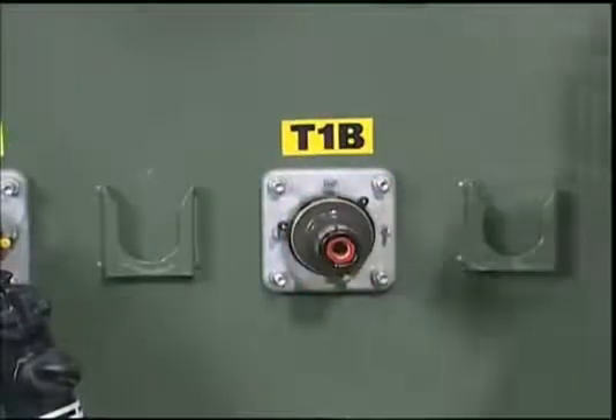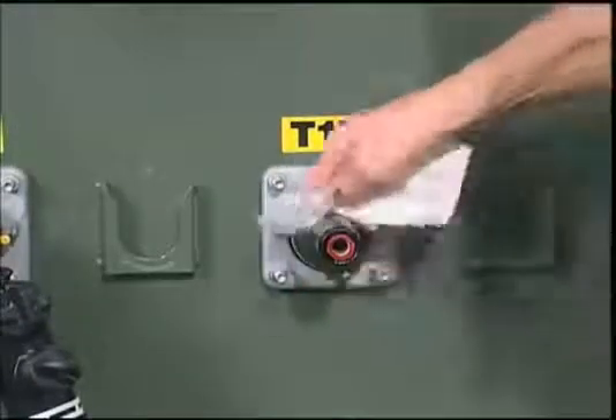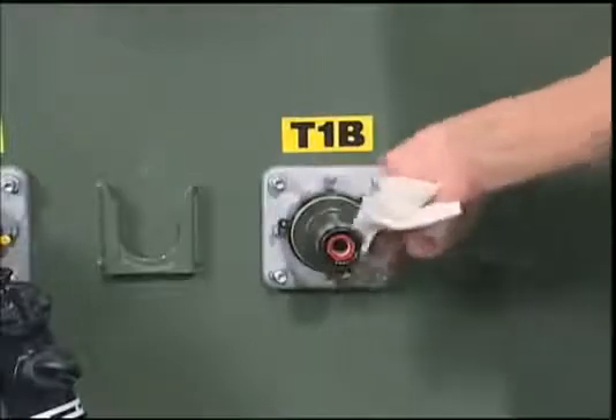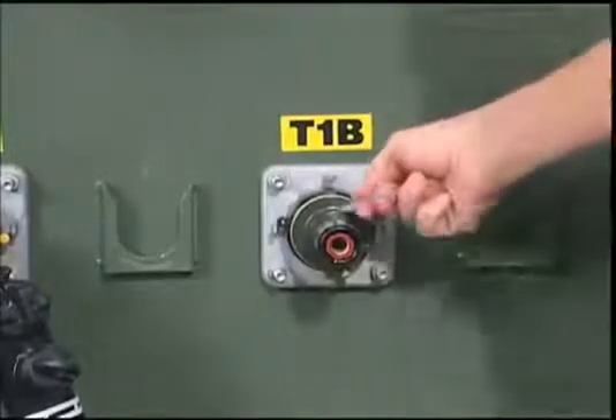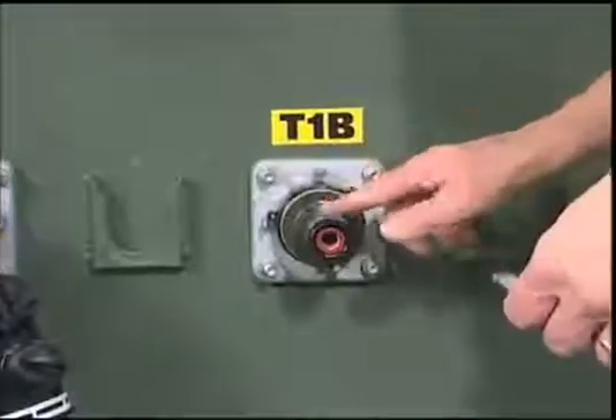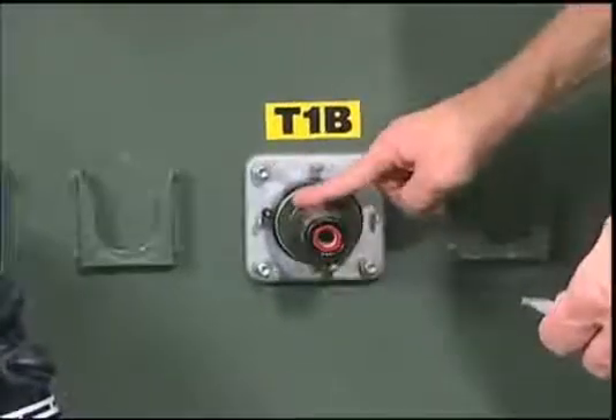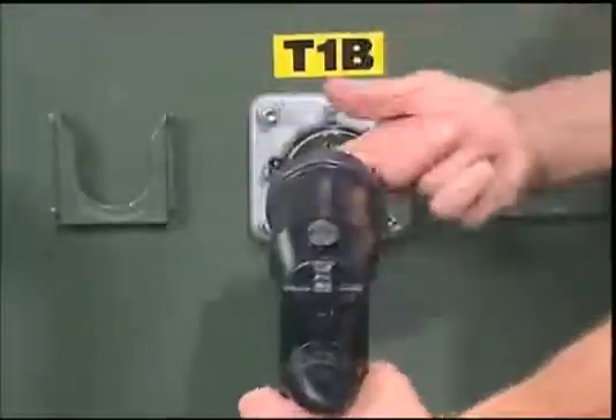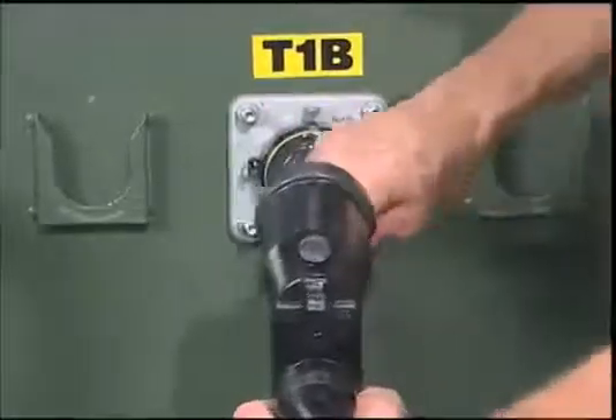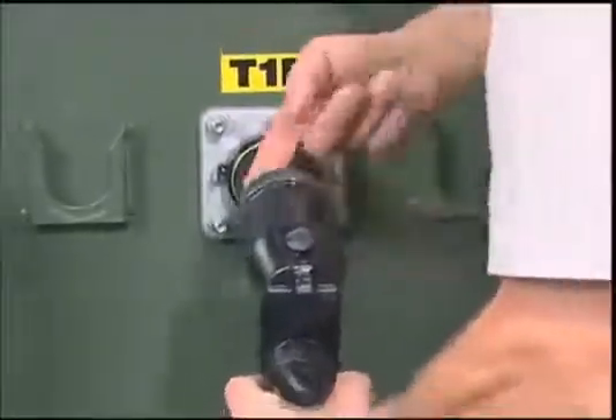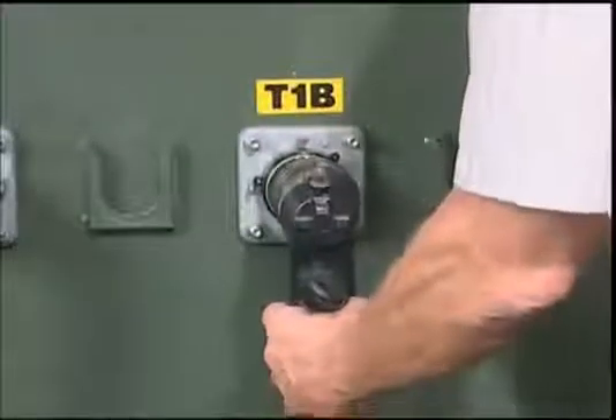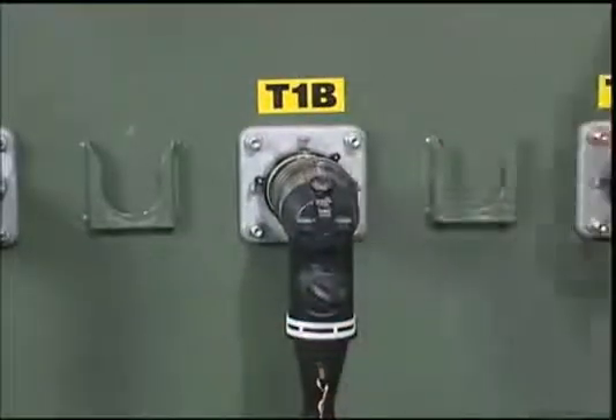Remove the shipping cap from the bushing insert. Clean the insert interface using a lint-free cloth. Apply a thin, evenly distributed layer of silicone grease to the interface, including the shoulder. Then apply a thin, evenly distributed layer of silicone grease to the inside of the elbow and the cuff. Now, position the elbow by hand.